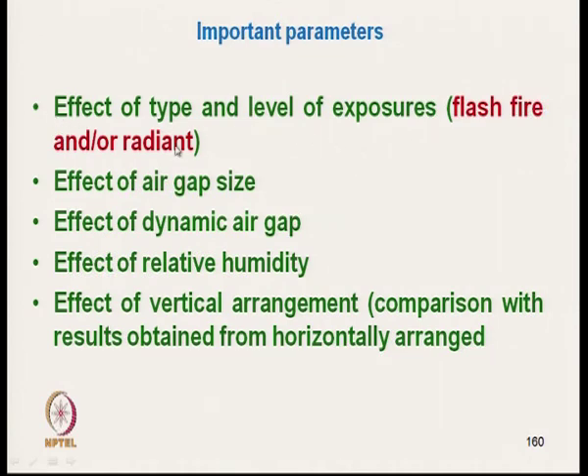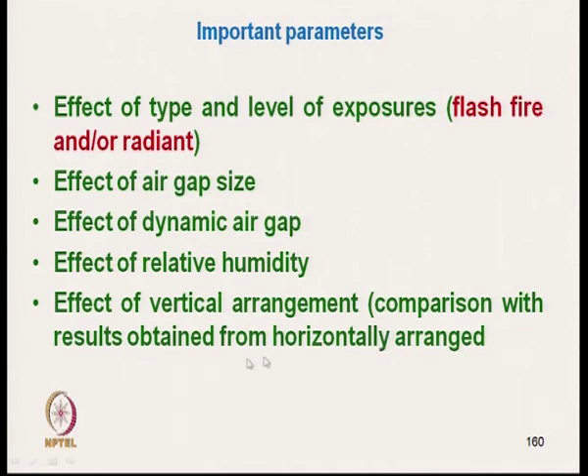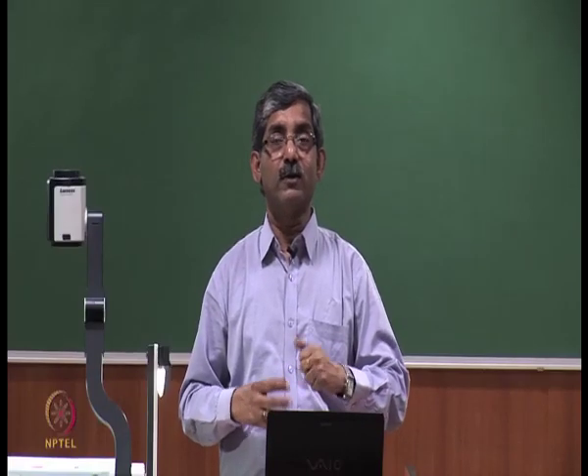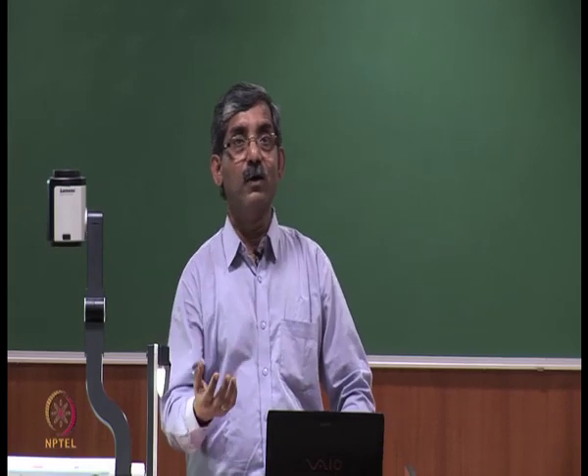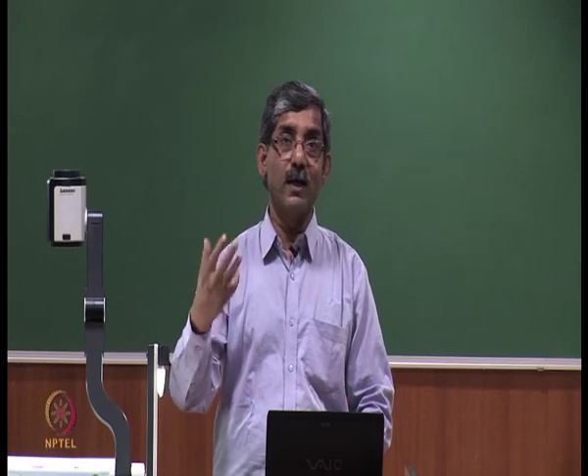The parameters that can be tested with this instrument include: the effect of type and level of exposure (flash fire or radiant), effect of air gap size, effect of dynamic air gap, effect of relative humidity, and effect of vertical arrangement with comparison to results from horizontal arrangement. This gives a wide range of information related to flame exposure and radiant heat exposure.